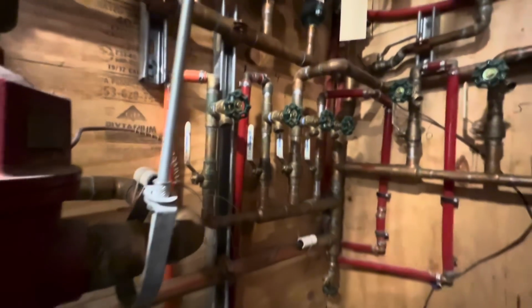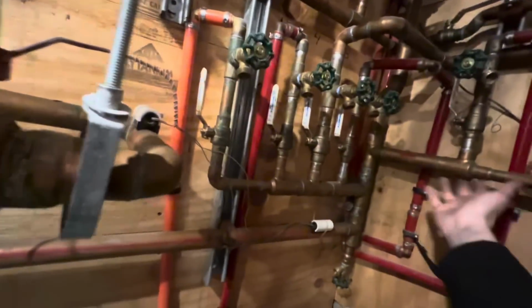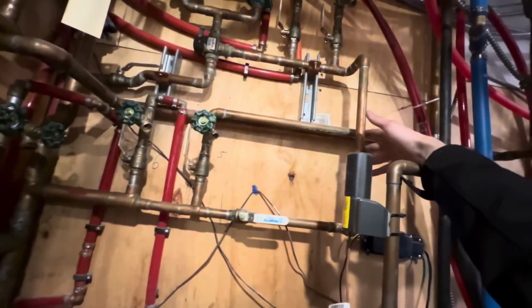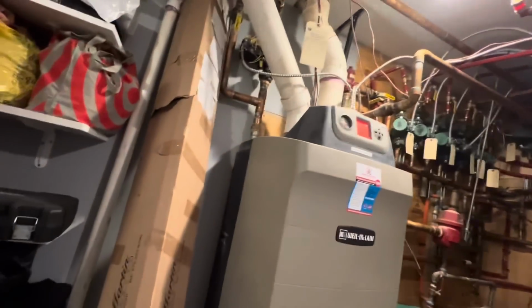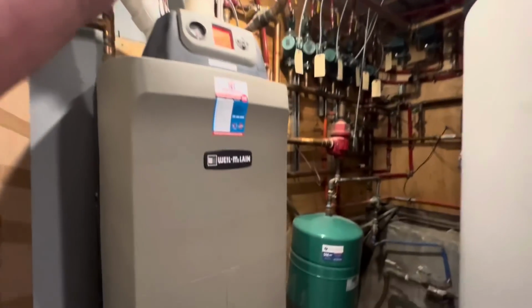So we come up there, we go. We have our indirect tank that's separate. We got this coming out, right? We go up and through into here, out to our zones, and then back through here. So this is our closely spaced T. Not very close, but it's been that way, so that's not going to be why we had an issue. I'm gonna bet it's our circulator pump for the boiler itself. Probably not moving water within the boiler.